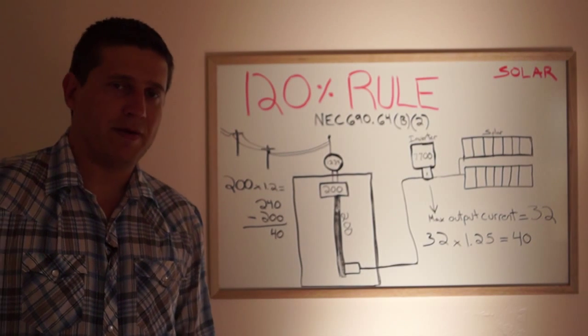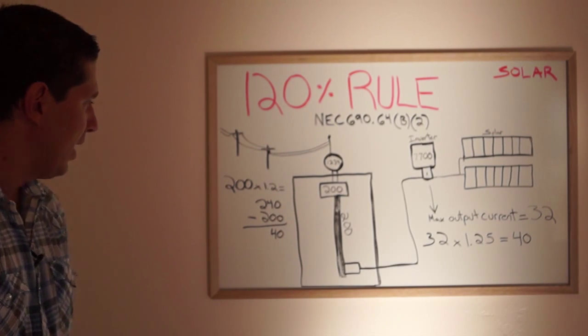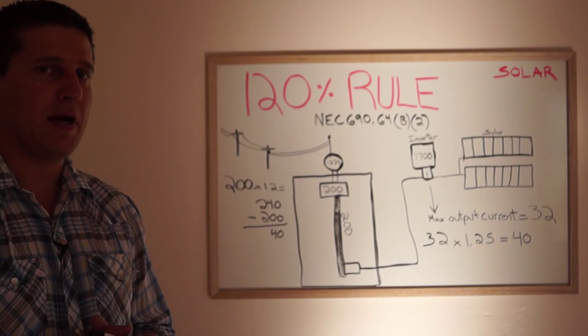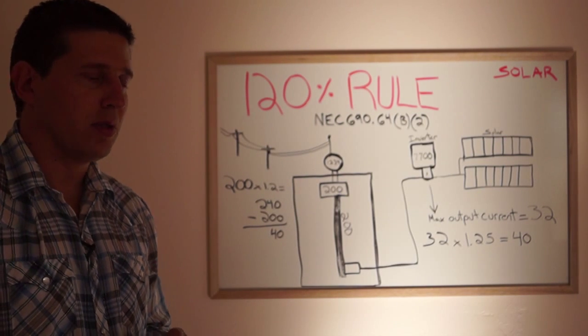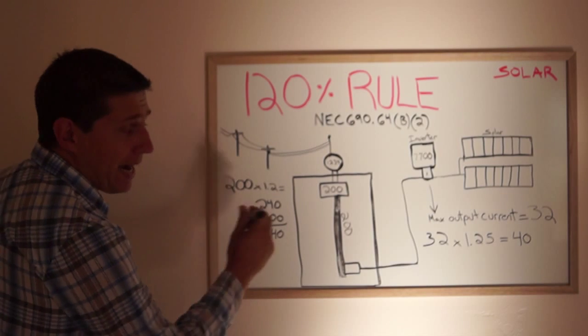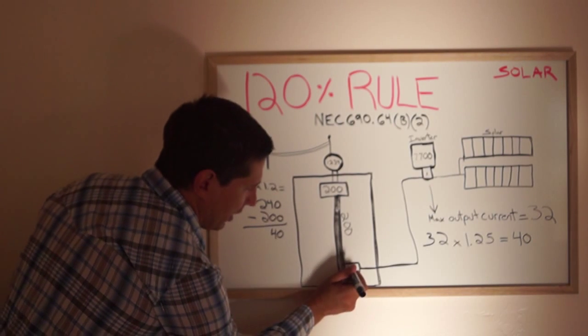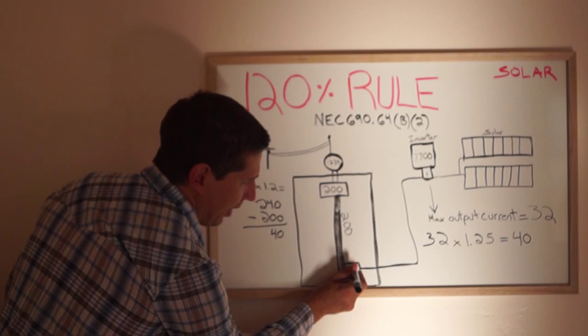The 120% rule states that you can't have more than 20% more of the bus bar capacity loaded with solar. So that means we have a max amps of the solar is 40 amps on that breaker.